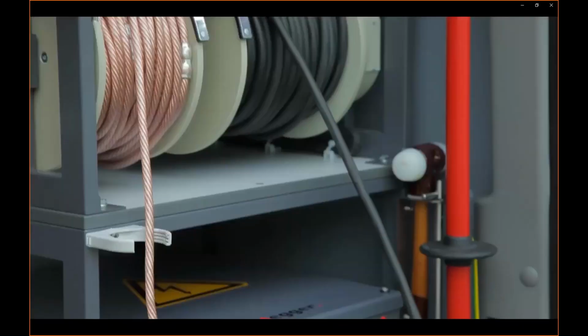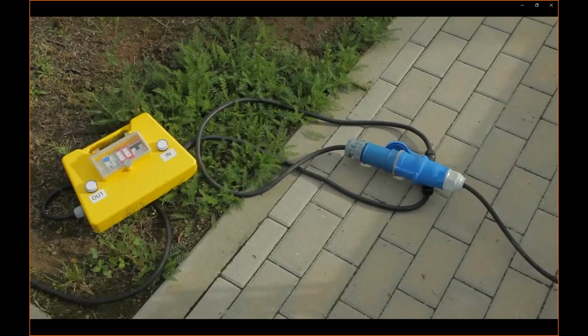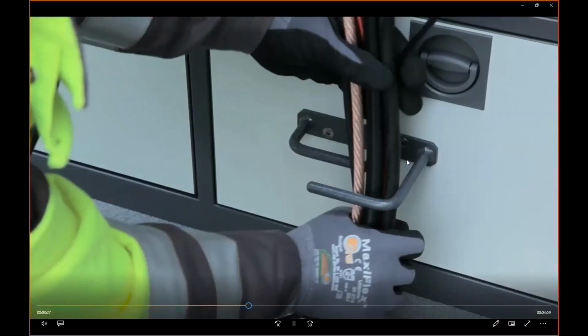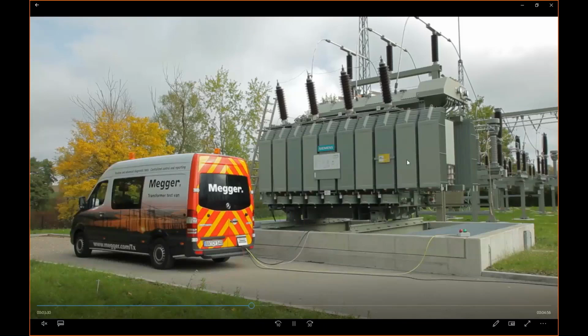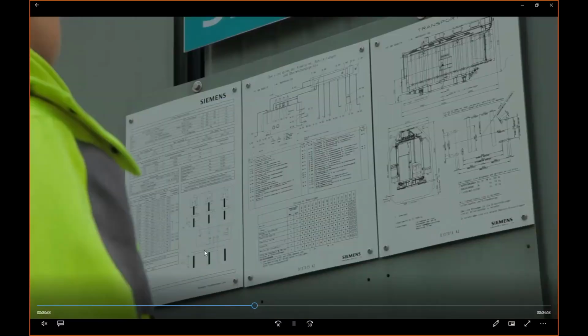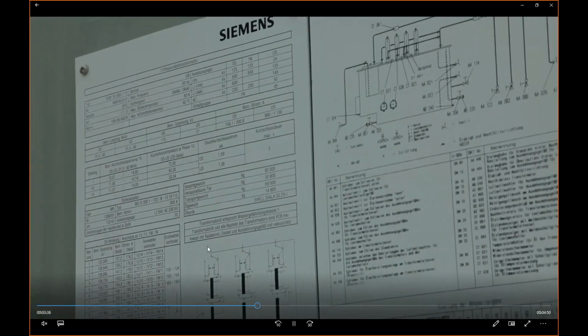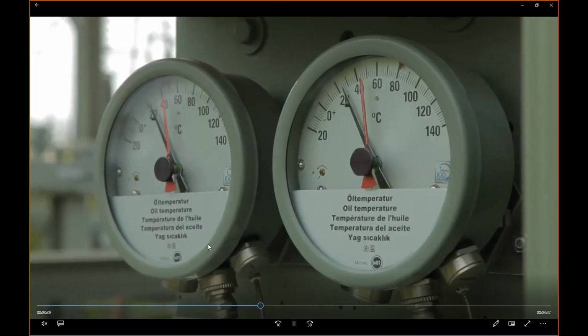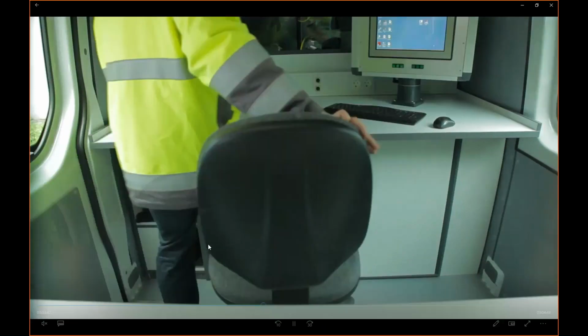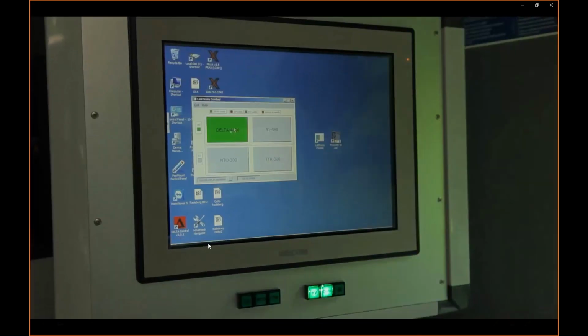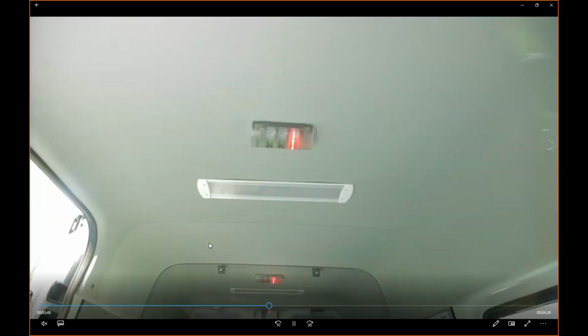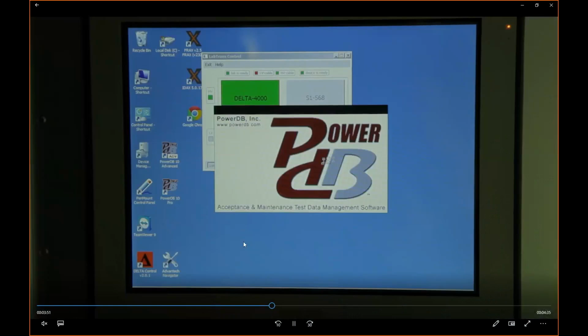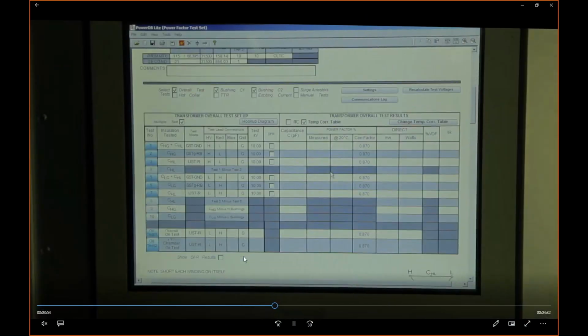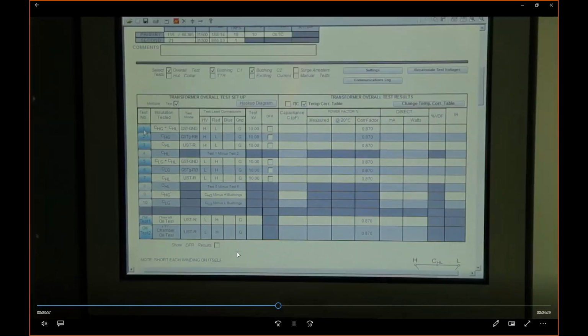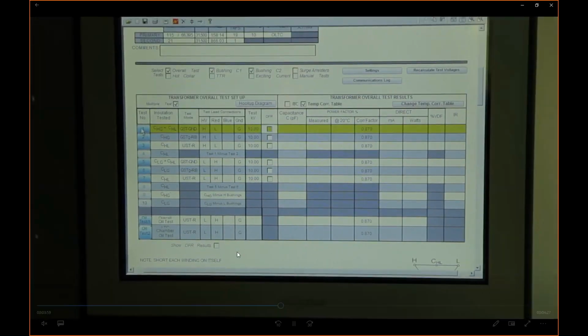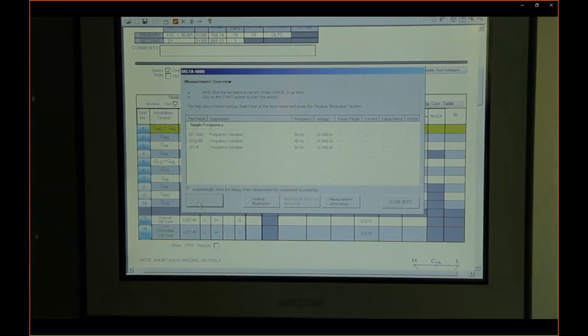Okay, so here's the power supply also shown. You connect it. We can provide a 3-phase power supply or single-phase power supply depending on the power ratings of this test van. So of course, since you are working with reports, you need to set up all the data, temperature and nameplate related. You activate the software, activate the instruments, and you see that the light turns red. And the database and the control software will guide you line by line, collecting the data and forming your reports for the condition assessment.